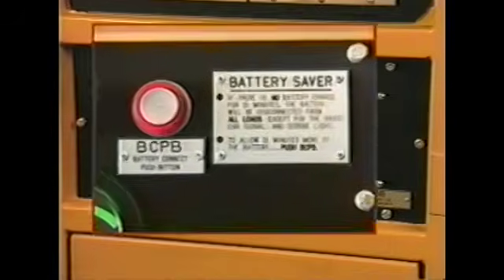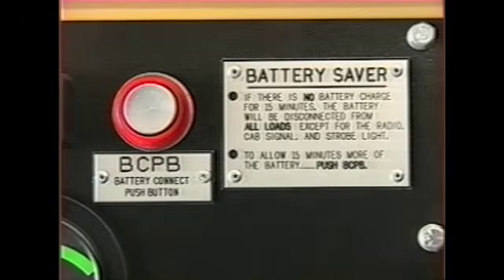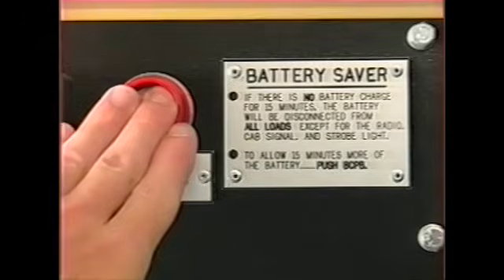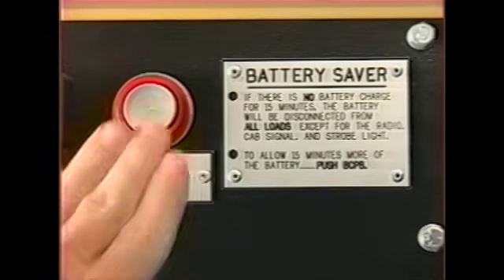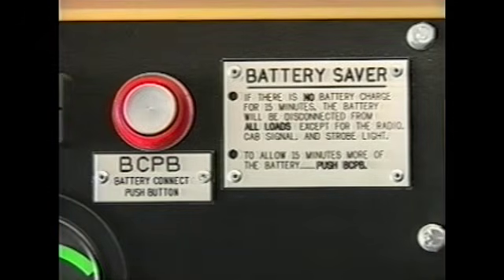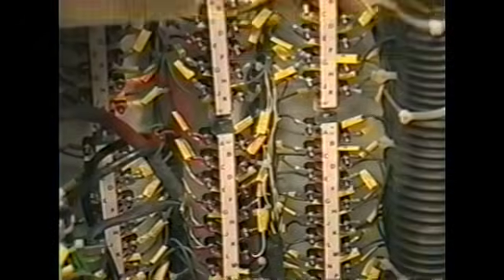The Battery Connect push button is another device on the lower section of the EC panel. Since the P42 battery saver circuit disconnects the batteries 15 minutes after the diesel engine is shut down, use this push button to reconnect the batteries before you start the unit. Critical circuits continue to be powered even when the battery save circuit is engaged.